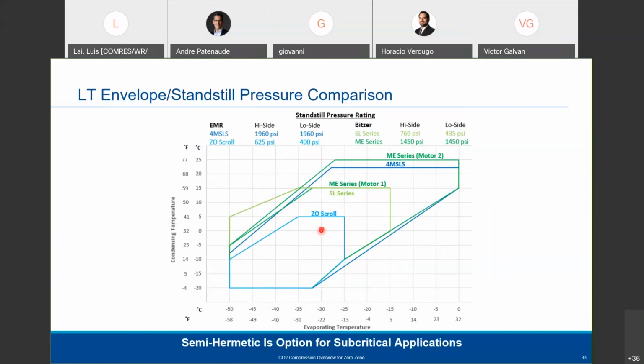From an operating envelope perspective, it sits right in here. The normal operating, it could be even lower in here depending on the condensing temperature, but somewhere in there. It can go all the way down to -58 Fahrenheit with a head pressure of about 14 degrees and so on. So you follow that line. Compared to the Bitzer Motor 1 version, their Motor 1 version has a wider operating envelope, and then their Motor 2 is even wider, of course.